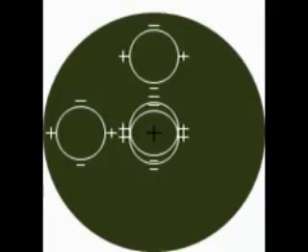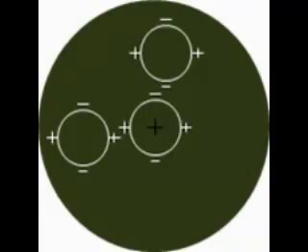Turn the elevation knob if the plus sign is not in the center. Once the plus sign is in the center of the focusing circle, the optical axis of the instrument will coincide with the patient's visual axis. For this particular instrument, focusing does not depend solely upon the sharpness of the target mires, but is accomplished by coinciding the double focusing circles into one circle.